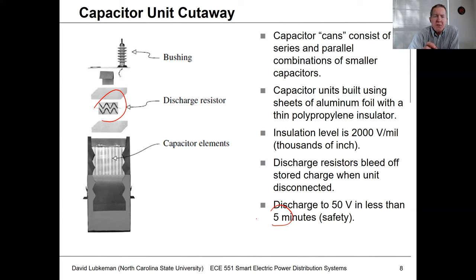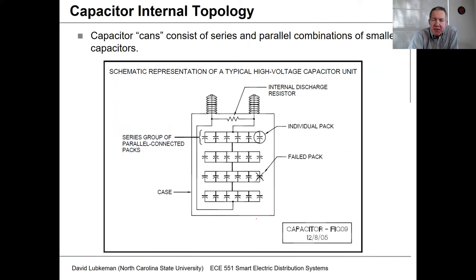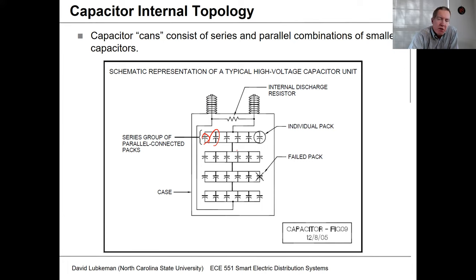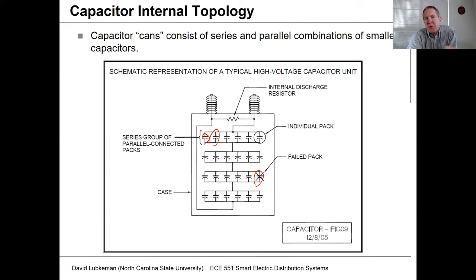Inside each can are miniature capacitances made of metallic foil arranged in various series and parallel combinations. One reason for this is fault tolerance — if there's an insulation failure somewhere, it doesn't take out the whole capacitor can, just causes a small loss of VAR support. This is how utility capacitors are actually constructed.